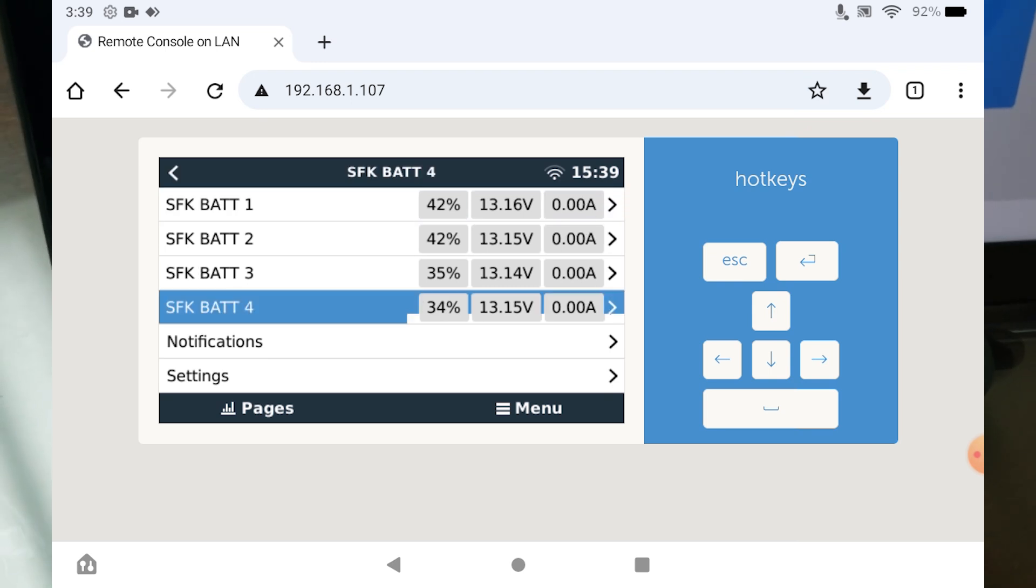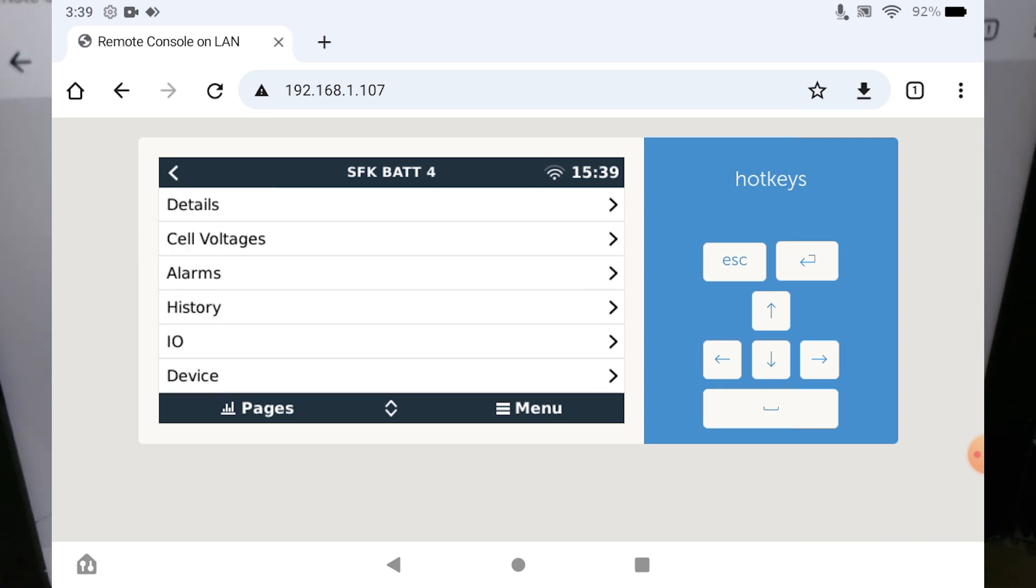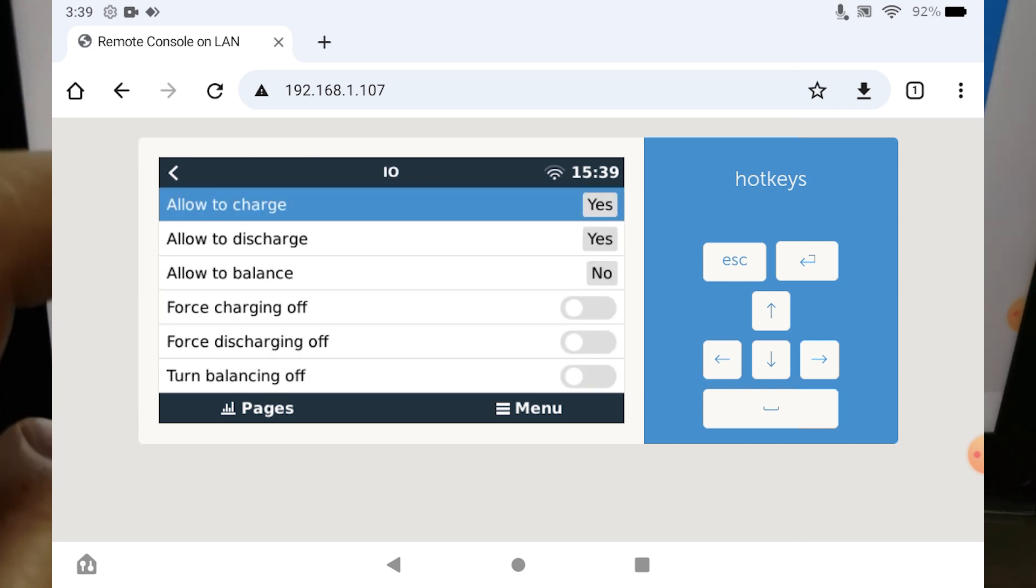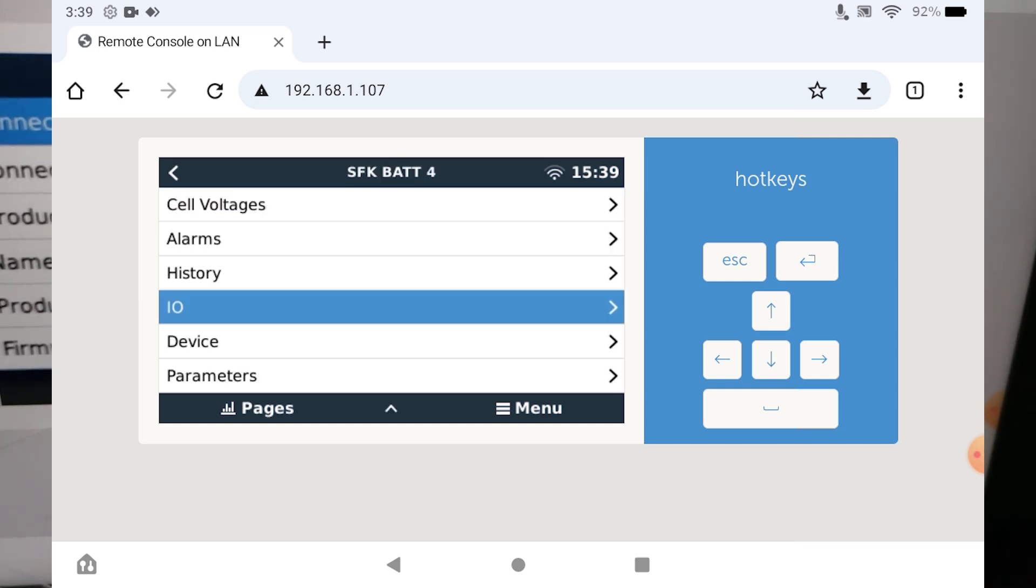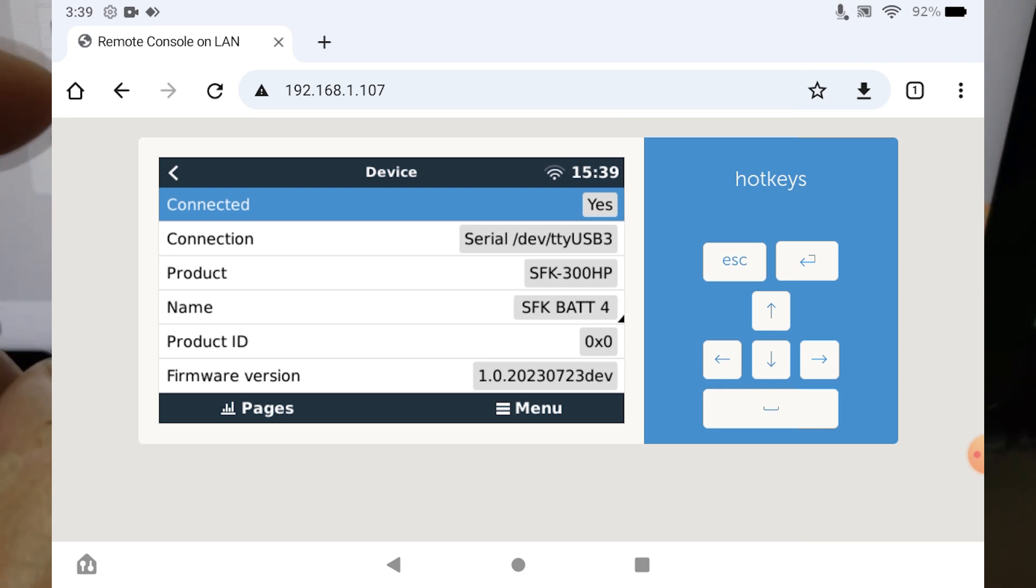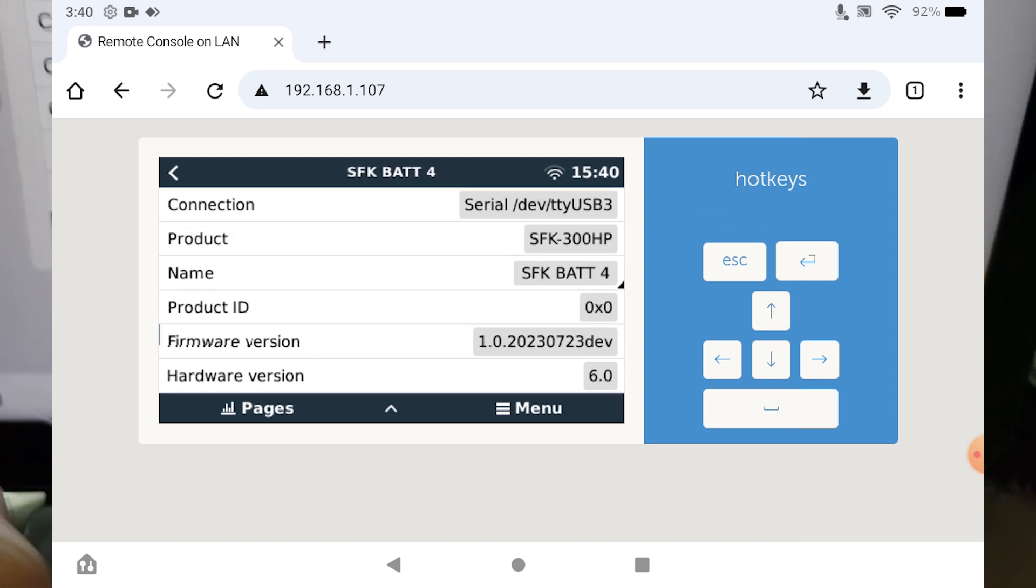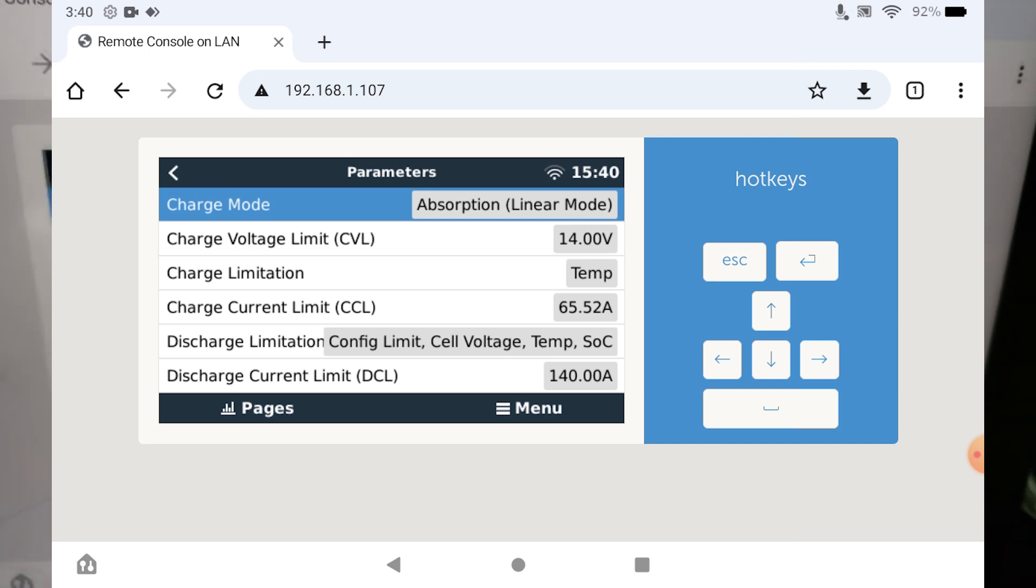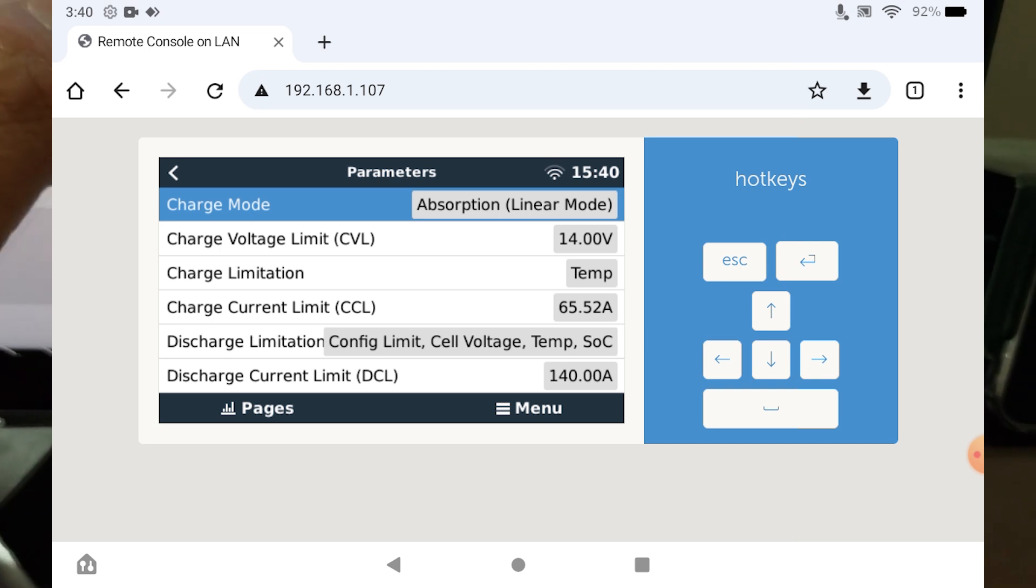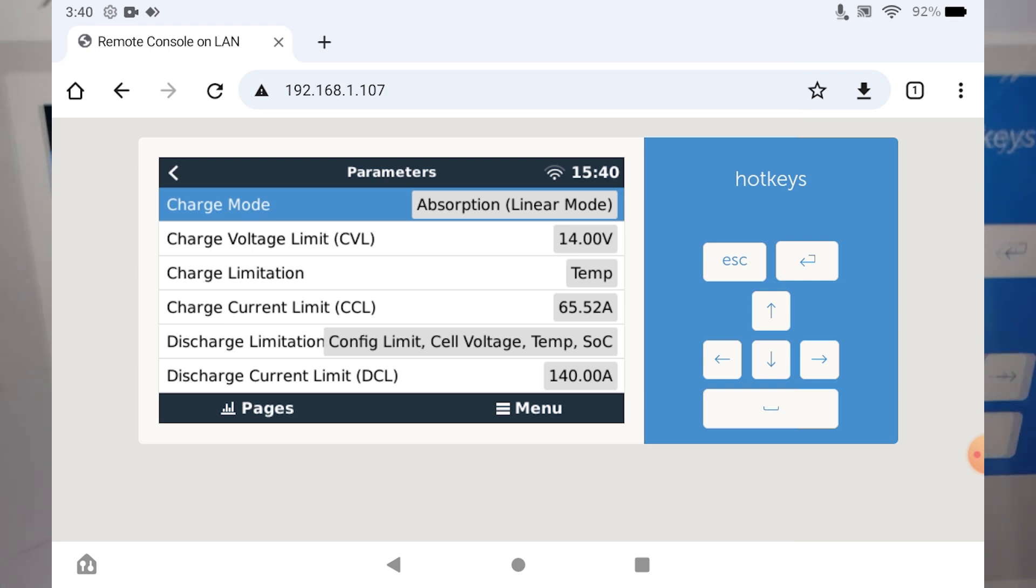You can get the data in here and you can go in here and see some IO and some settings. And what that does is you can decide if you want the Cerbo to handle different things such as allow to charge and allow not to charge. And you can get device information - like it will say that these are 300 HP batteries and auto assign the name for them. You can set certain parameters, you can set up what sort of charge mode it is. Like we've set it to 14 volts as its peak - you can go to 14.4, but 14 should be sufficient. And this will do some of the things that we have said as a default. For example, we have said 140 amp discharge limit per battery.